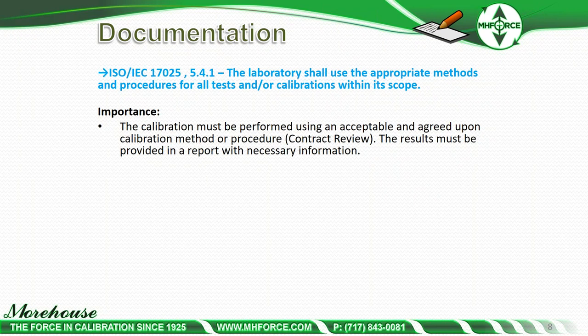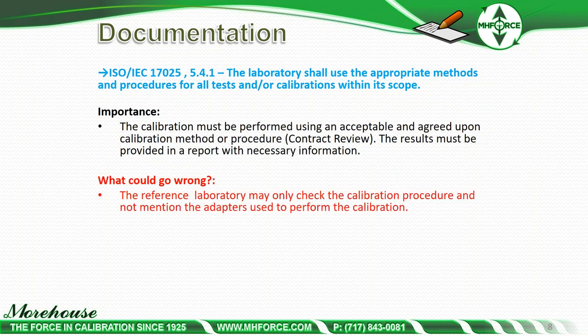We should ask the right questions: do you have top adapters, have you sent them, do you need them ground? All things pertinent to your instrumentation and the calibration. What often goes wrong is the reference laboratory may only check the calibration procedure and not mention the adapters used. When we do the calibration, we try to reach out and get more information. Sometimes it's bothersome to the customer, but we want to ensure you get proper results — there may be several calls back and forth regarding indicator settings, adapters, or cable labeling.